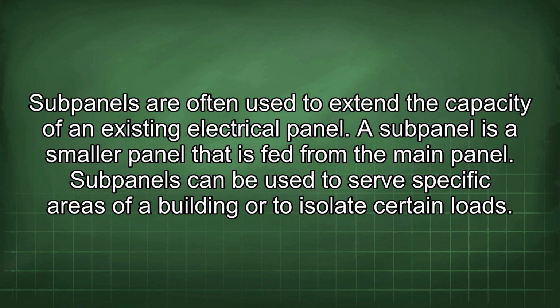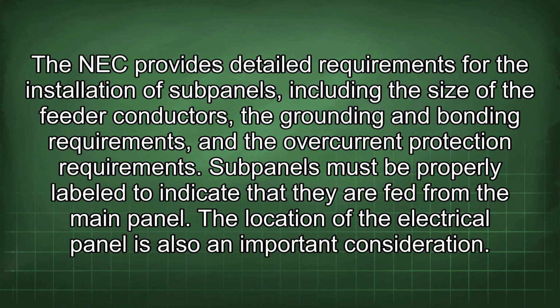Subpanels are often used to extend the capacity of an existing electrical panel. A subpanel is a smaller panel that is fed from the main panel. Subpanels can be used to serve specific areas of a building or to isolate certain loads. The NEC provides detailed requirements for the installation of subpanels, including the size of the feeder conductors, the grounding and bonding requirements, and the overcurrent protection requirements. Subpanels must be properly labeled to indicate that they are fed from the main panel.